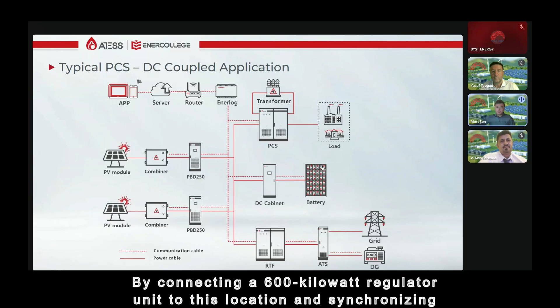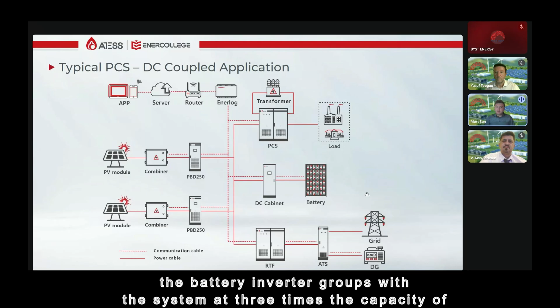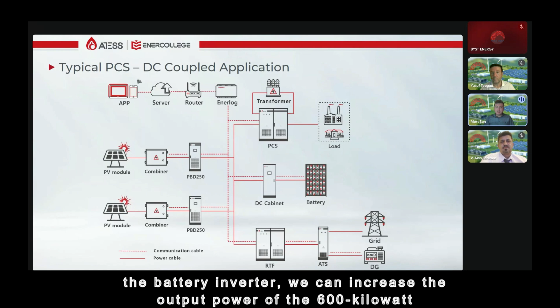Here, by setting up our method, for example, there is a 630 kilowatt transformer. By connecting a 600 kilowatt regulator unit to this location and synchronizing the battery inverter groups with the system at 3 times the capacity of the battery inverter, we can increase the output power of the 600 kilowatt transformer to 1 megawatt at 400 volts. Here, our customer doesn't lose any time. Now they are completely supplied with harmonics-free clean energy.